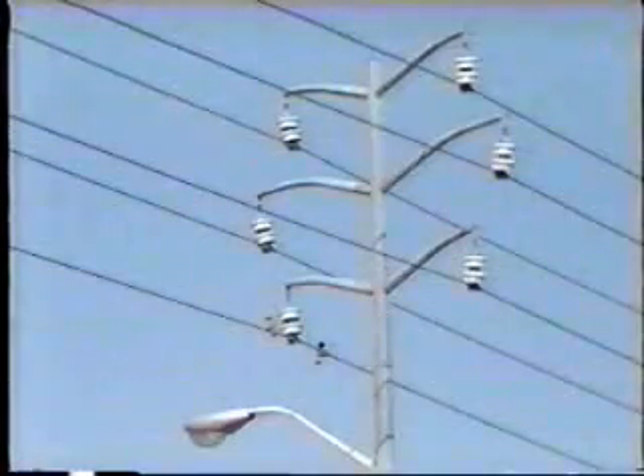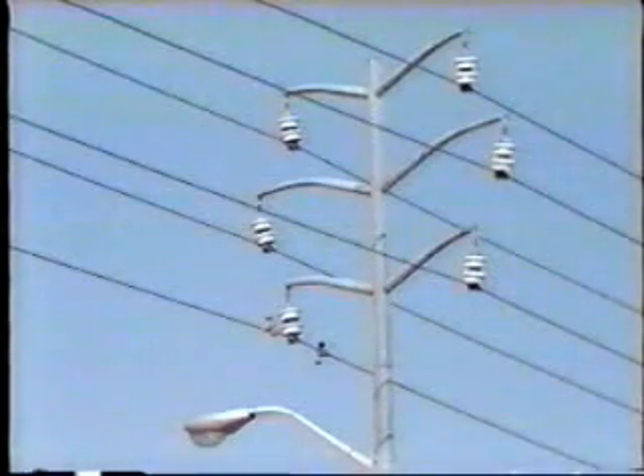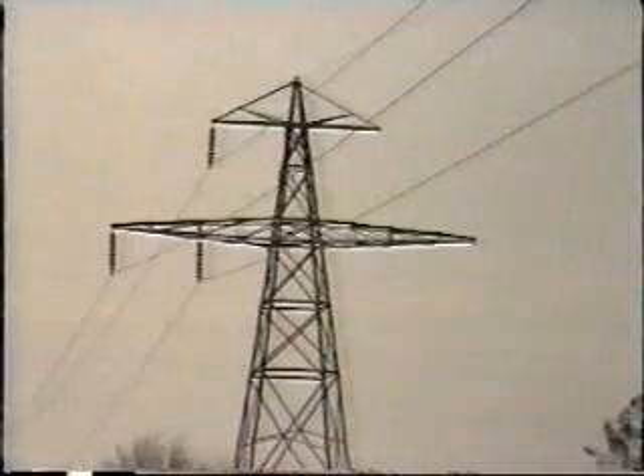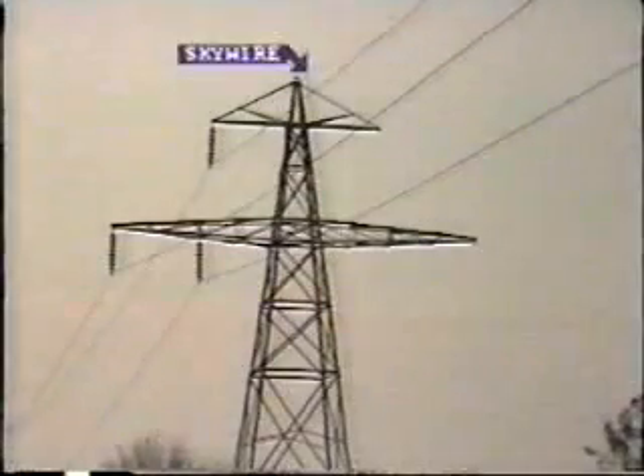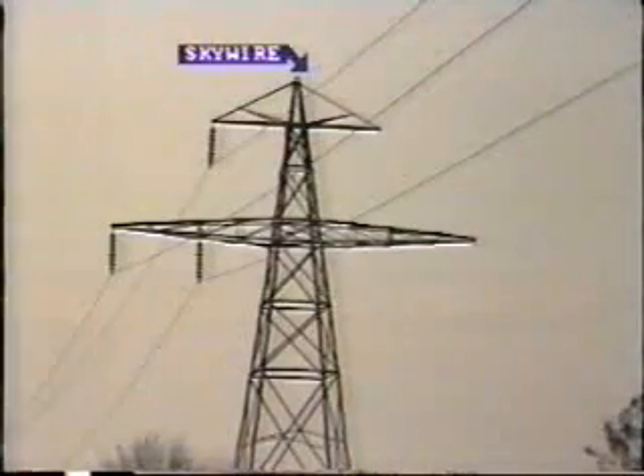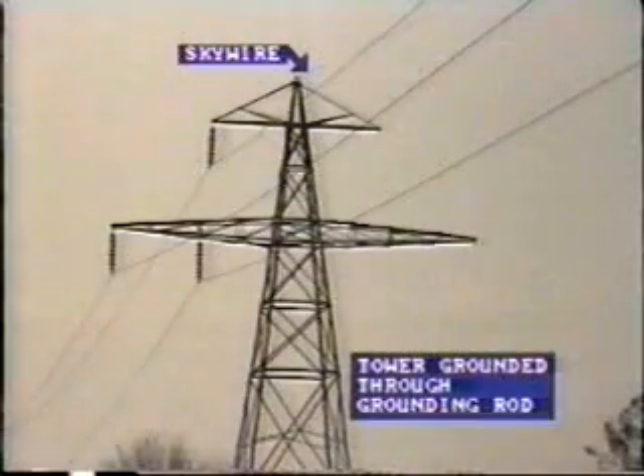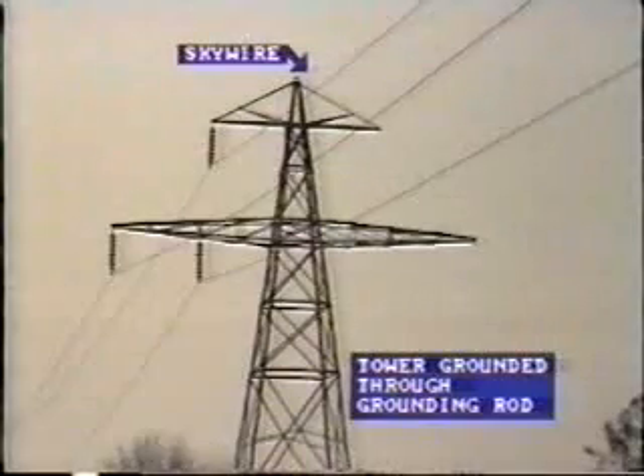Sub-transmission and transmission lines which carry higher voltage are usually supported on steel towers, although wood structures are still used in some instances. Only 3 conductors are run as the load is considered to be balanced. Usually a grounding wire is connected along the top of the tower, both to act as a shield against lightning and also as a conductor for ground currents. The foot of each metallic tower is also grounded through a grounding rod.